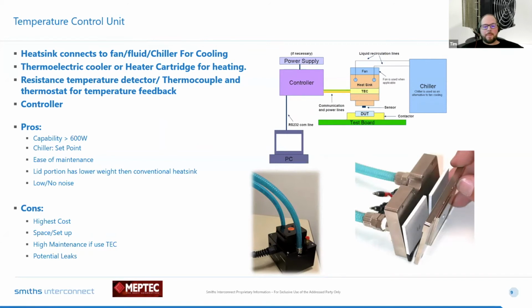Thank you. So to follow up on what you just said, say you want the silicon to be at a certain temperature during the test. Then you have to characterize what set point to set your chiller, so that during the test the silicon gets to the desired set point.